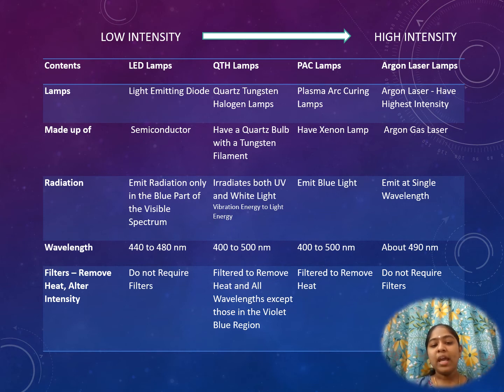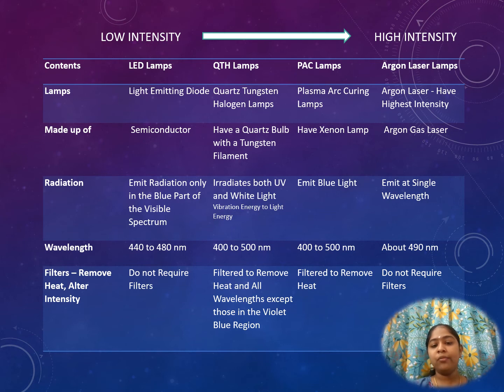Filters — why are filters used? They remove heat, alter the intensity required, and remove unnecessary wavelengths. In LEDs, filters are not required. In QTH lamps, filters remove excess heat and all unnecessary wavelengths except those in the violet-blue region. PAC lamps remove heat using filters, while argon lamps do not require filters.